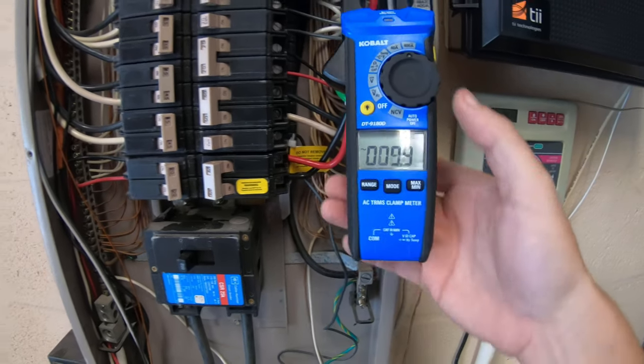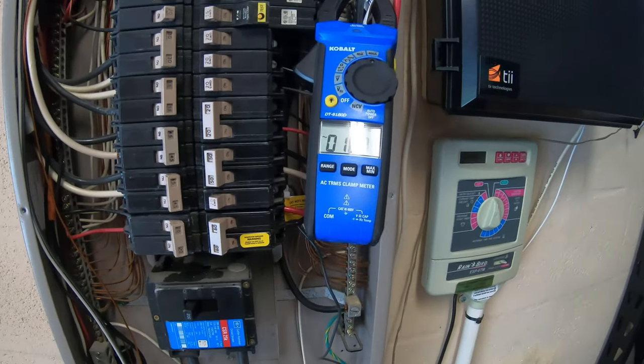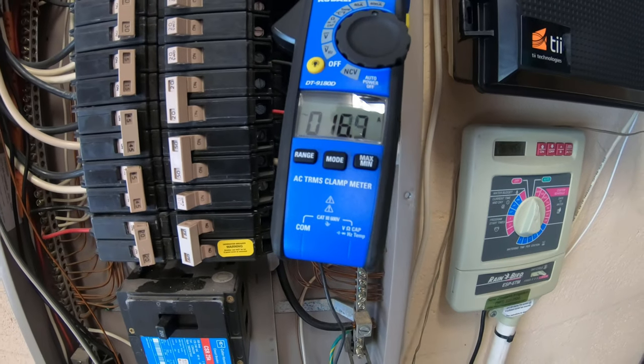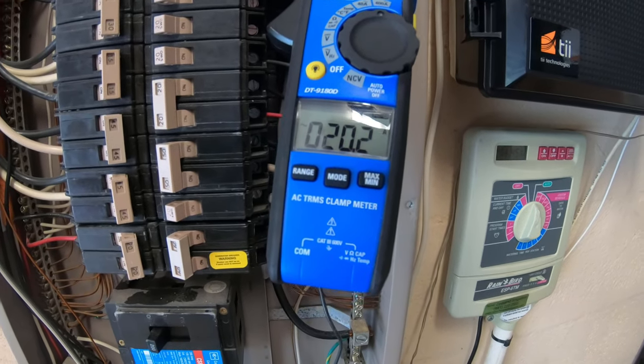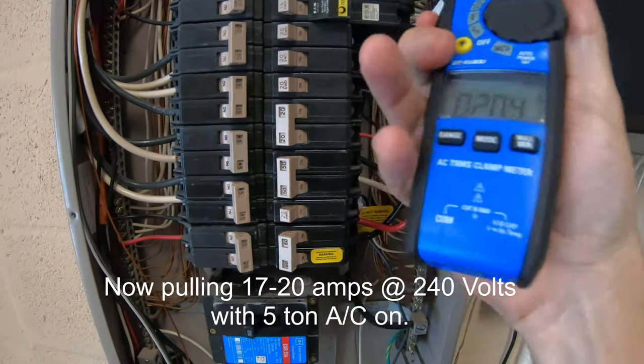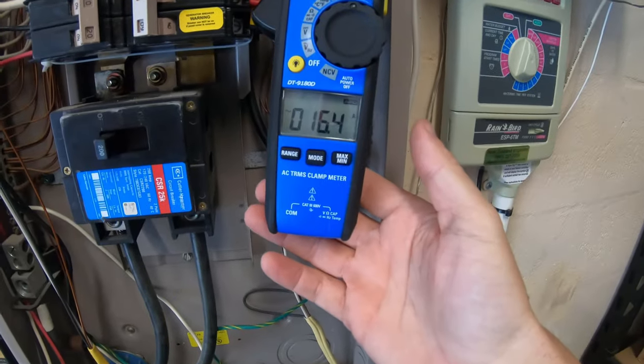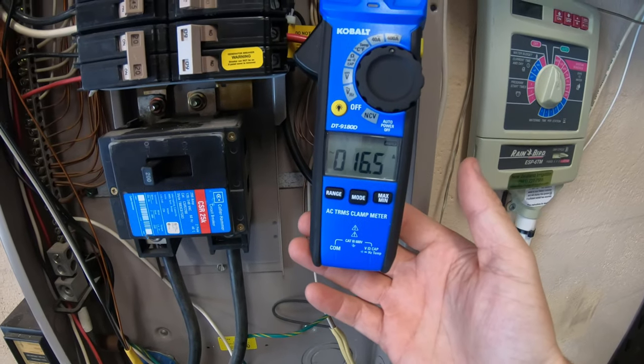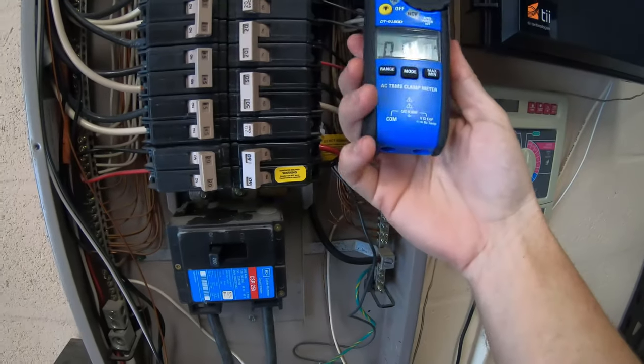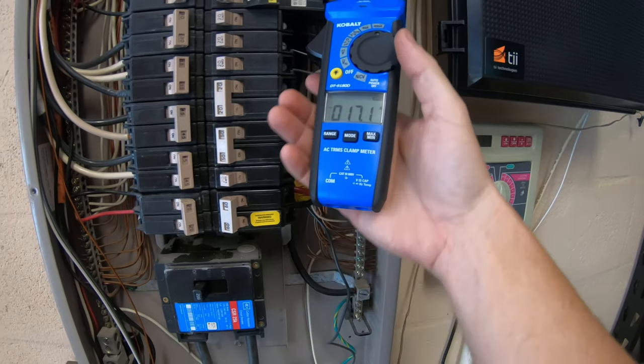10 amps baseline. 16.8 amps with the five-ton AC running — they were at 20 amps before. The AC is two-stage, I believe, so that one went up two. 16.5 amps on one leg and 17 amps on the other leg.